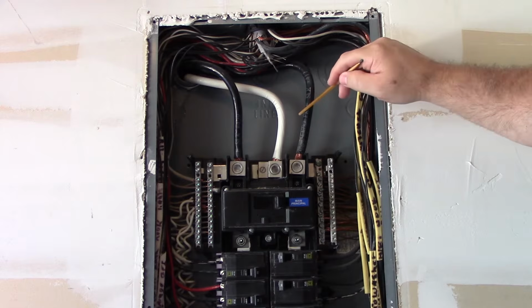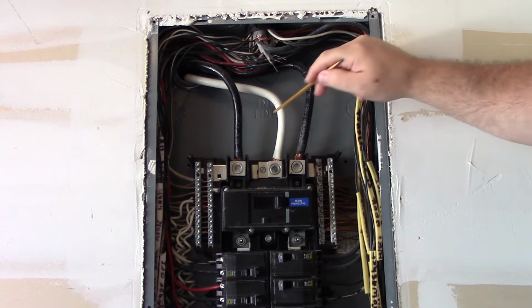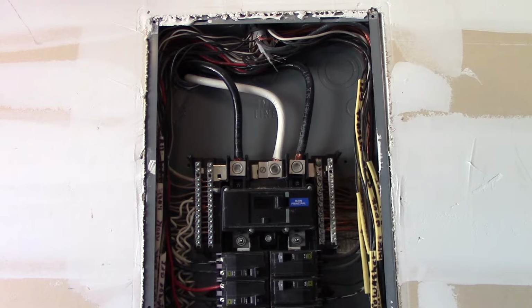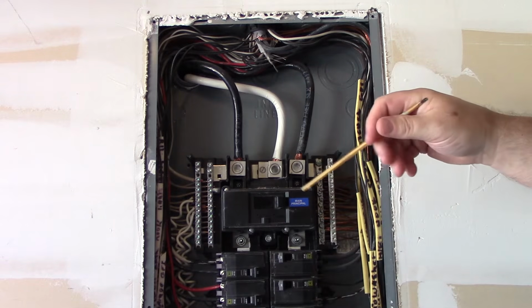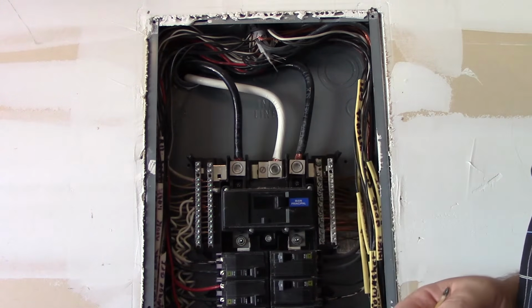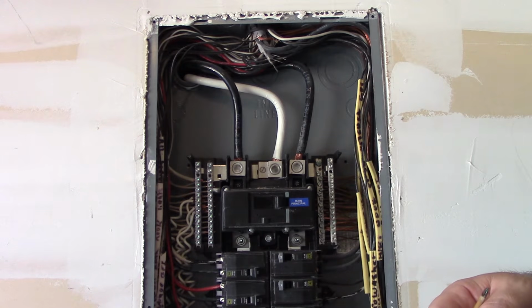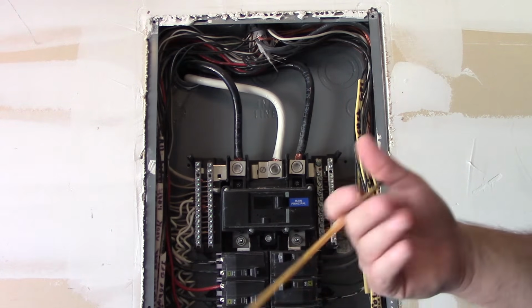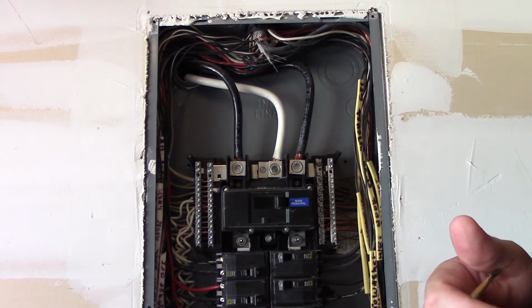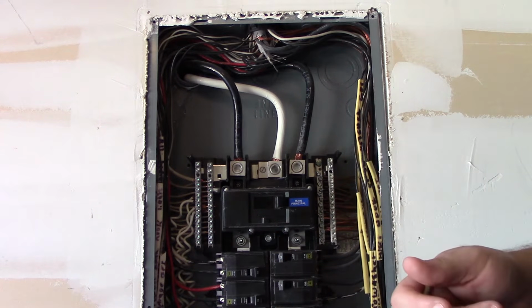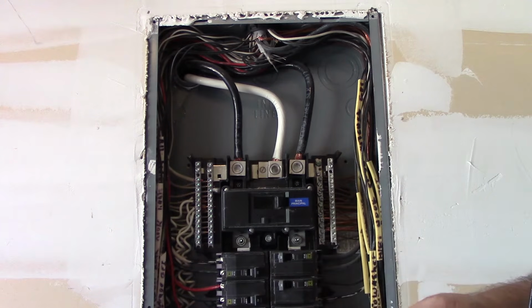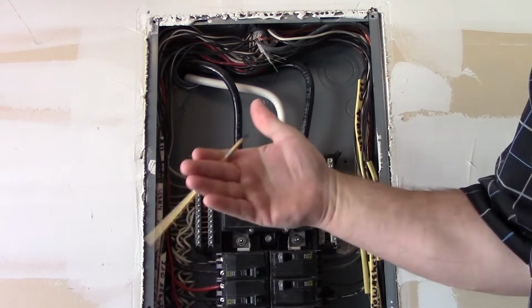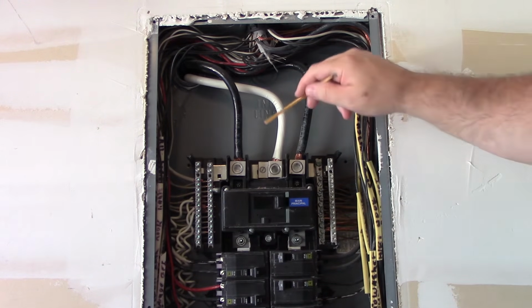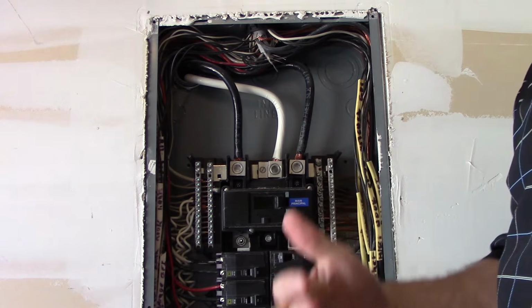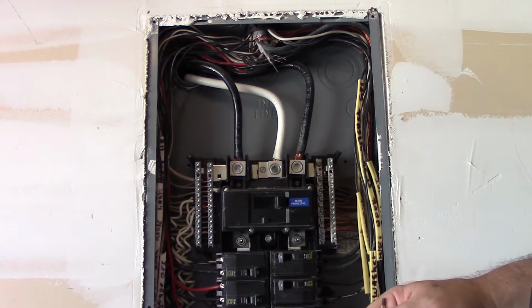Because on a remote distribution panel, you're going to need to run 4 conductors: 2 hots, a grounded conductor, and an equipment grounding conductor. So you need 4 conductors at a remote distribution panel. Okay? For some of you home inspectors, early on when you get to some old inspections of some old detached structures, you might see only 3 conductors run to it. That was prior to the requirements found in 250.32, which now requires that you run 4 conductors, a separate equipment grounding conductor and a separate grounded conductor out there, and you separate them when you get to that remote panel. Okay, so that's evolved over the years, so just keep that in mind if you're dealing with an older type of detached structure.